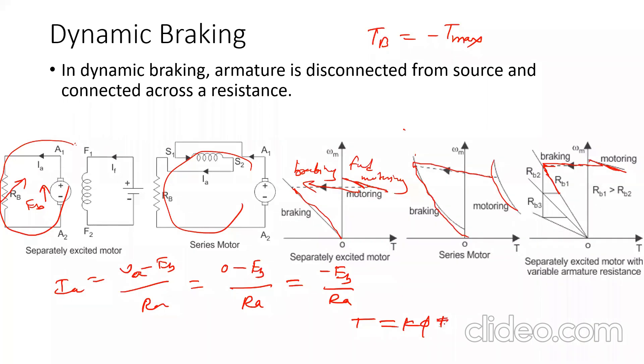We know that T = K·phi·Ia. Using that equation, the braking torque Tb equals minus K·phi·Ia — the minus sign comes because of the reversed direction of armature current. To maintain maximum braking torque, which depends on the value of Ia, and since Ia depends on Eb which depends on speed via Eb = K·phi·omega_m, as speed decreases Eb decreases and so Ia decreases. Therefore to maintain maximum braking torque, the braking resistance must be reduced progressively.